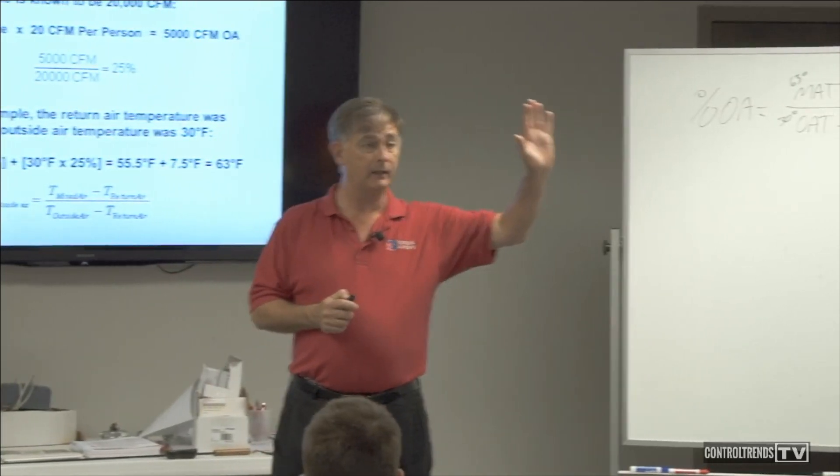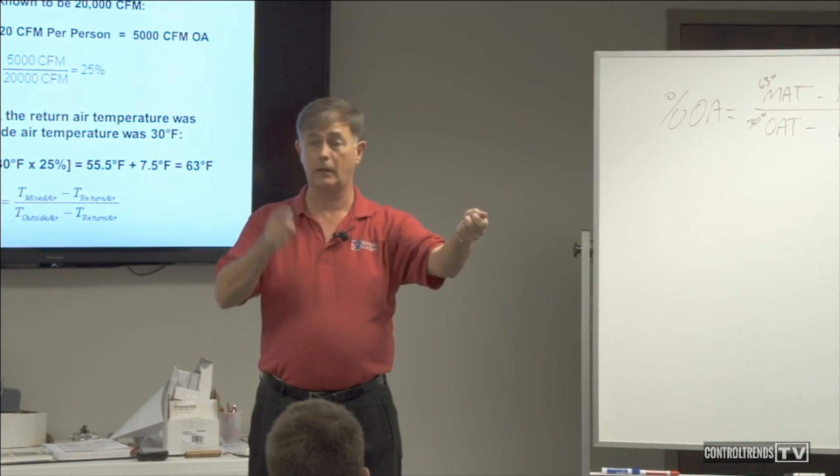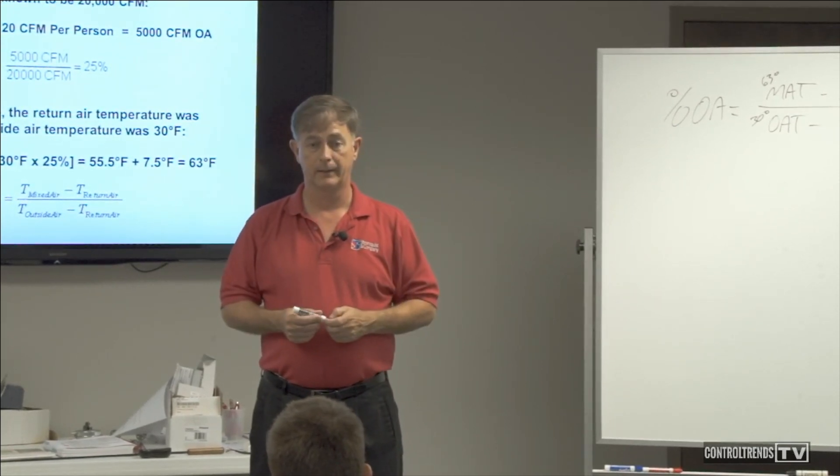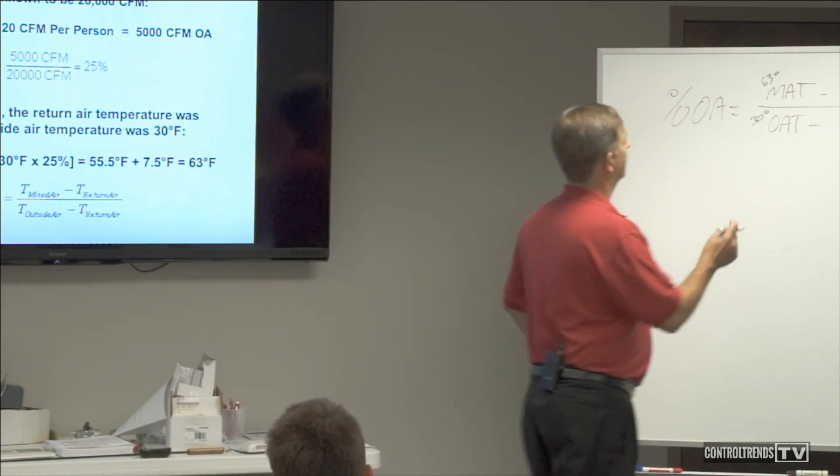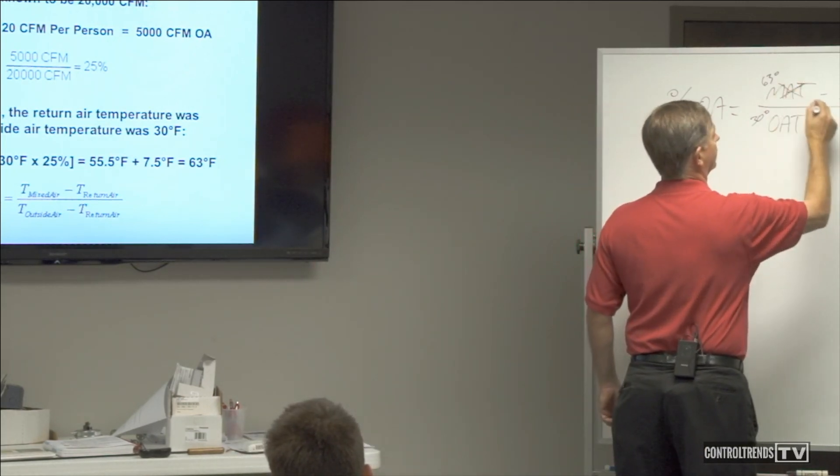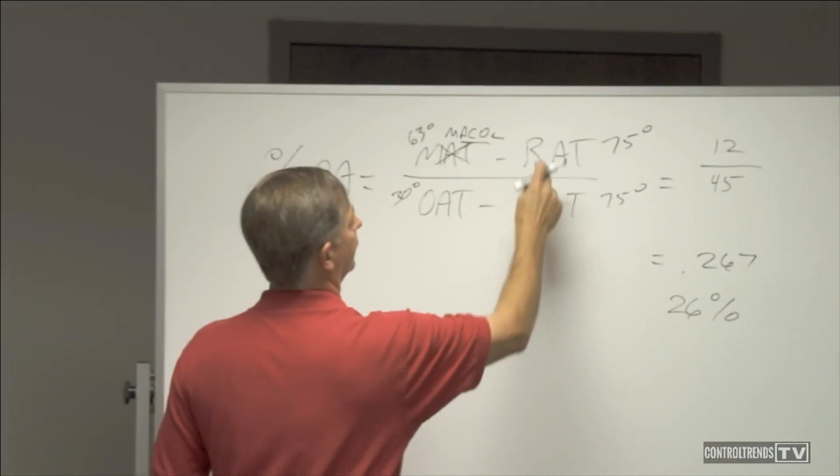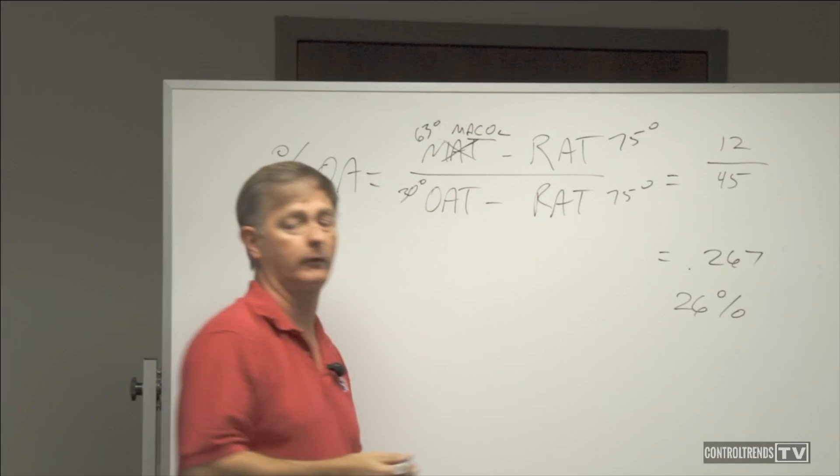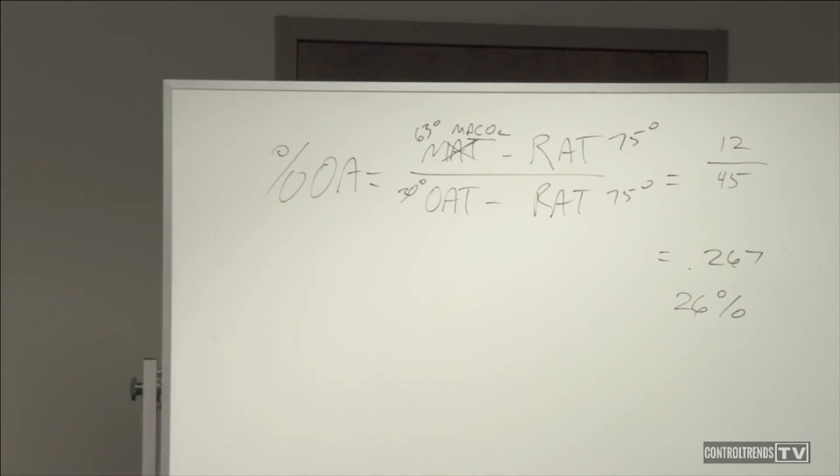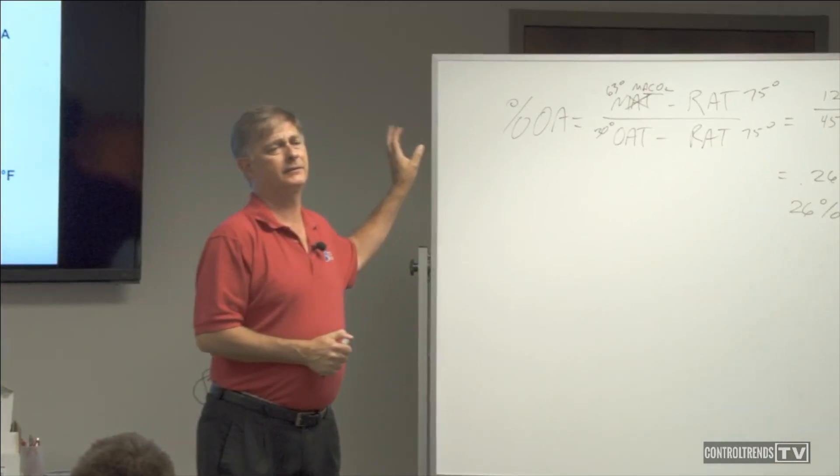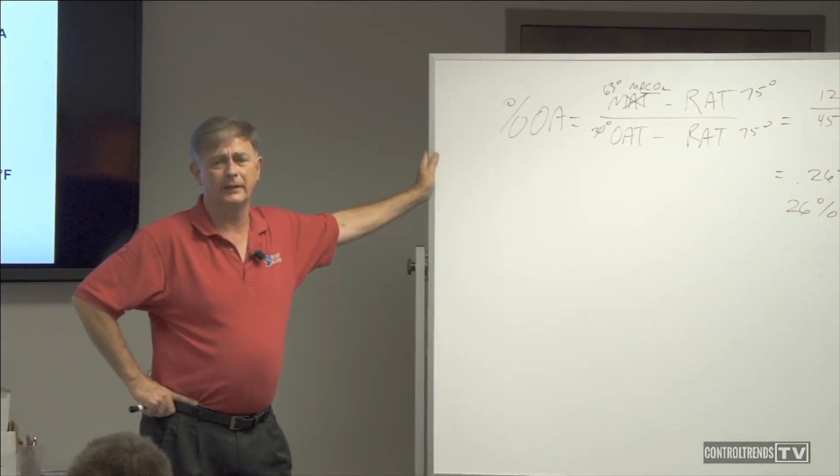Does anybody have a handheld CO2 sensor? A couple. It's not a prevalent device, at least amongst us. It's a handy device to have. What if we exchanged our temperatures for CO2 reading? So it'd be your mixed air CO2, your return air CO2, outside CO2, return air CO2. Now, the temperature is irrelevant and the CO2. Of course, if you have a CO2 meter, you can go to the floor and do it direct. But do you see how it's such an easy exercise?